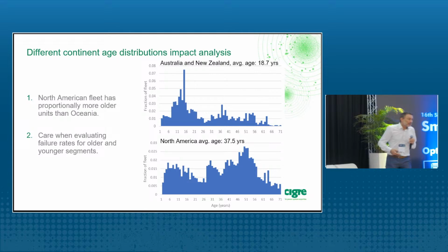And as I started working with power transformers, it was always said the average age or the expected lifetime of a transformer is 30 years. So the design should be good enough to survive 30 years. And if you go to North America, you can see the average age is already 37. So more than 50% are exceeding the 30 years. So normally, if that rule would be applied, most of the transformers would have to be exchanged.